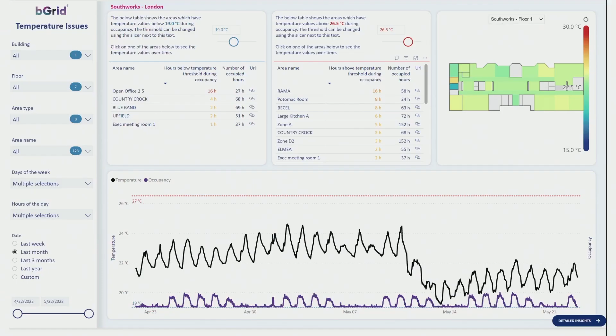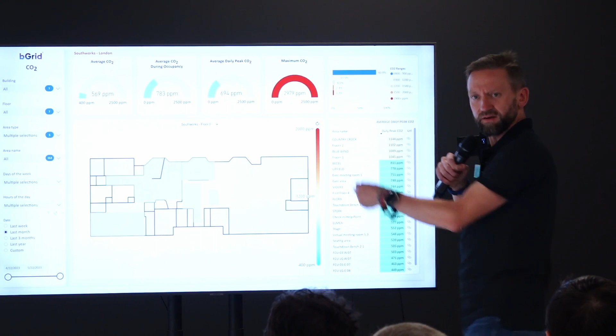CO2 sensors are also in the sensor network, but not in all of them - it doesn't make sense to have them in a really dense network. So we have CO2 sensors in specific spaces, like meeting rooms, because when you've got a confined meeting room, the CO2 level is really important. We can see there was potentially some issue with maximum CO2 in a space, but generally we're in the range between 400 and 900 ppm, which is absolutely okay. So generally the building performs okay, and there's some space where we potentially could have issues.